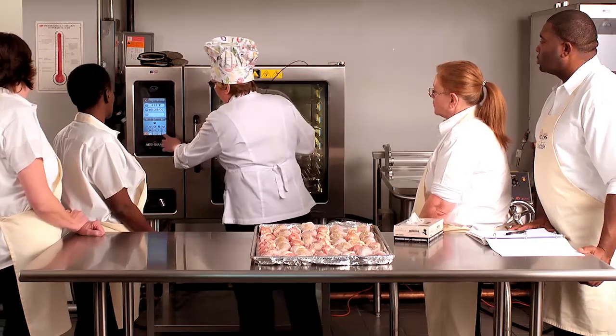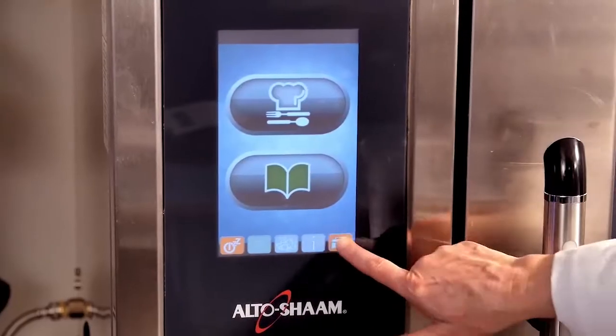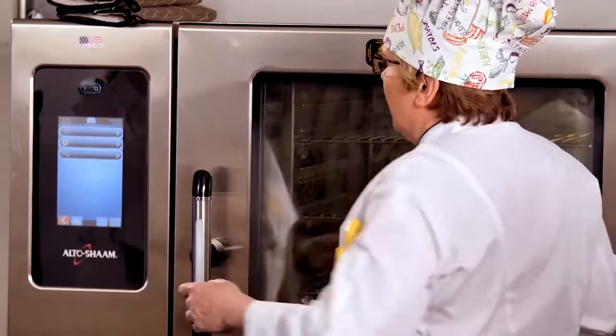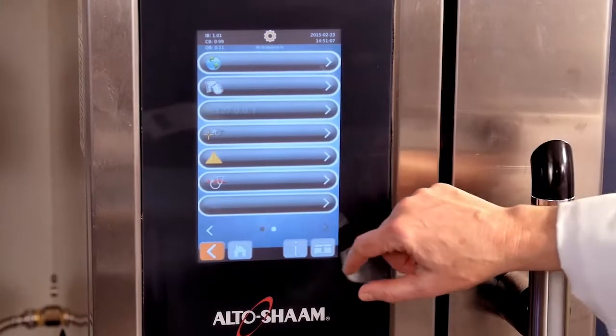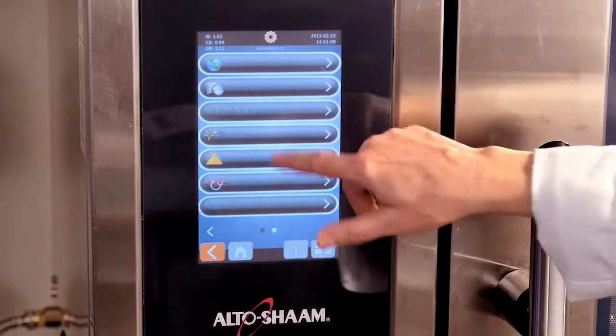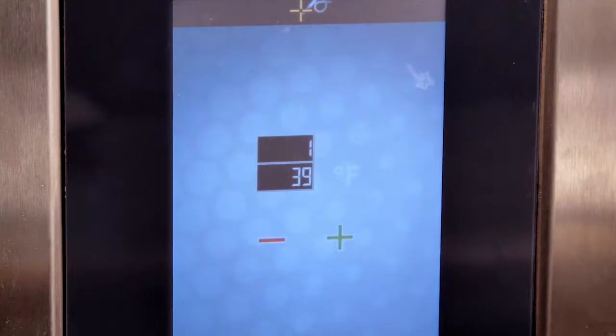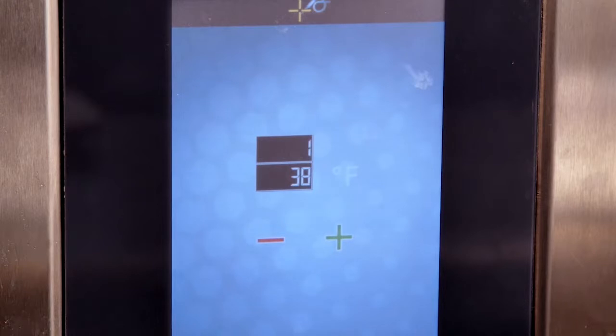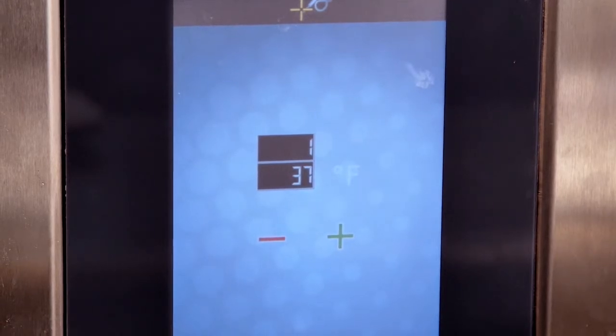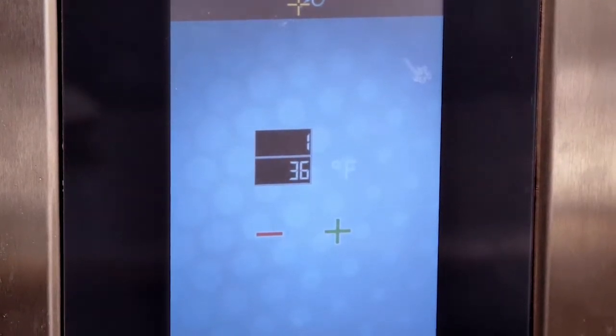On your panel—and every unit is slightly different, so check your operator's manual—we select the tab for calibration. Here you can see the numbers giving a readout of the probe's temperature, and you can see the numbers starting to drop.